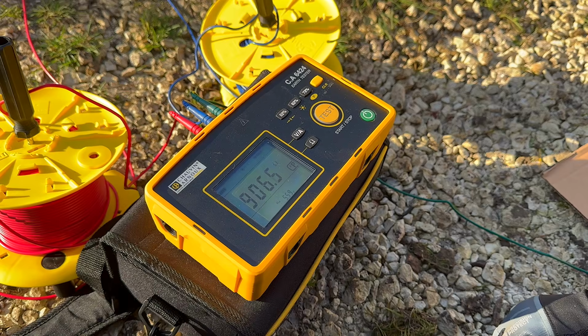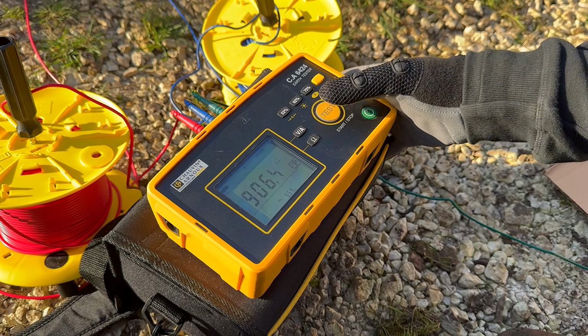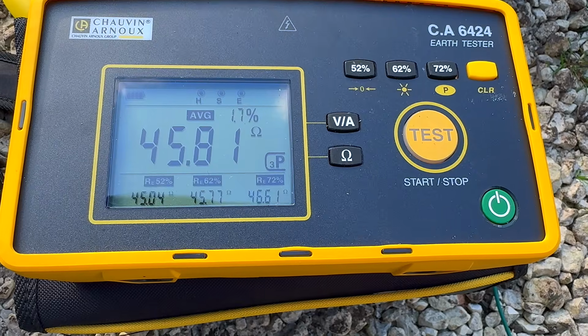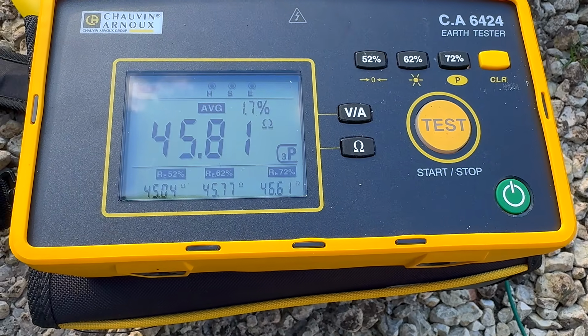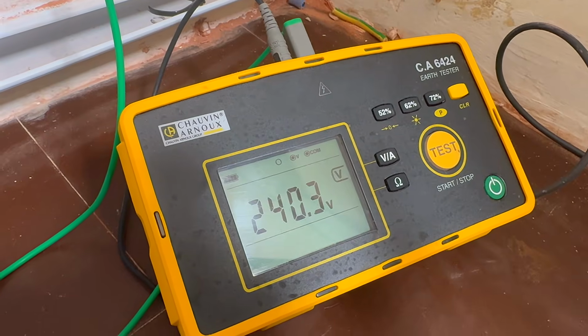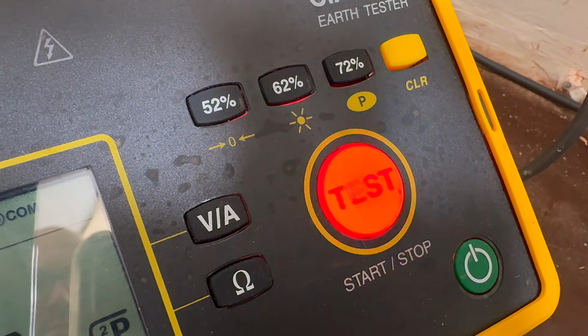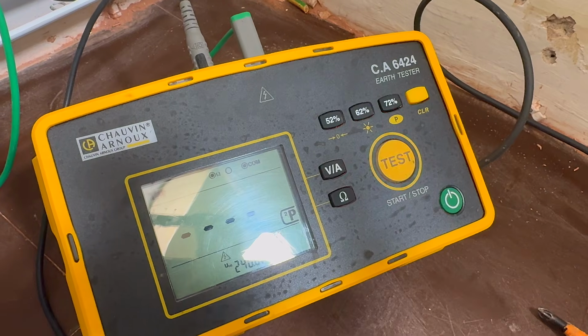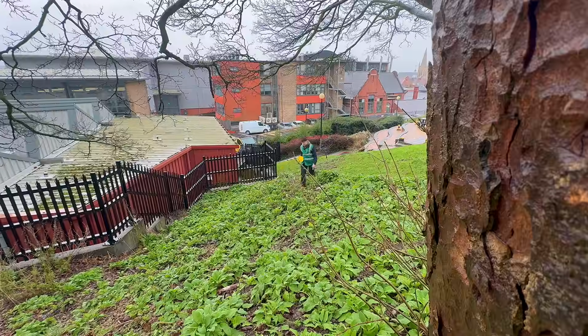All of the controls on the front panel are good quality, so you can operate it easily even with the gloves on. The screen is backlit and split into 3 displays, so you can see the measurement results, any errors and supporting information at the same time. There are also clear indicators. An LED warns if a hazardous voltage is present, and a noise symbol shows when external voltages could affect the reading. Okay, on with the test.